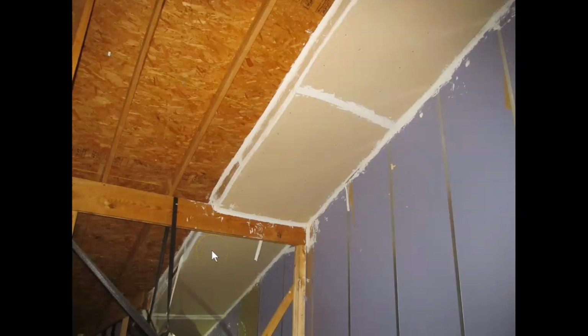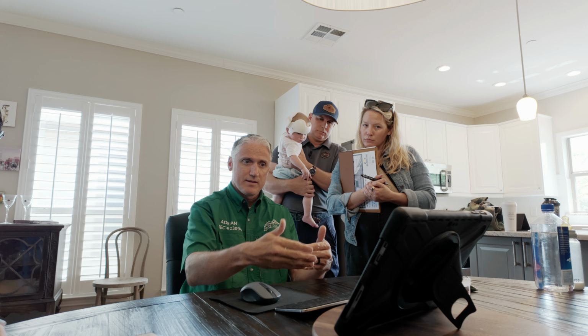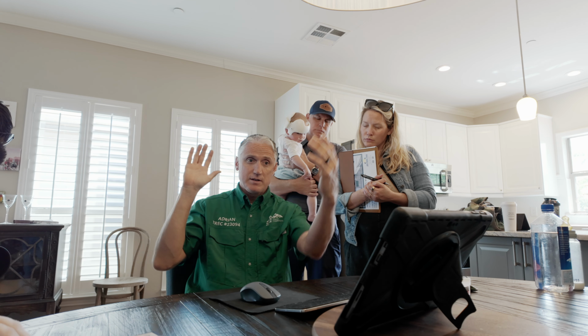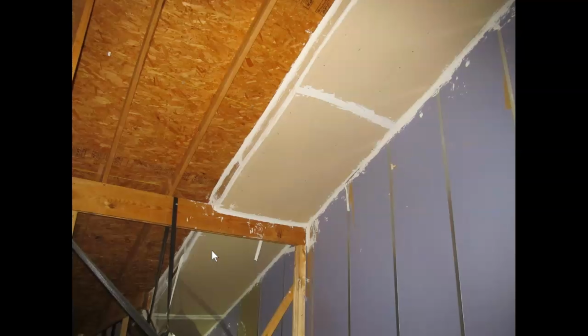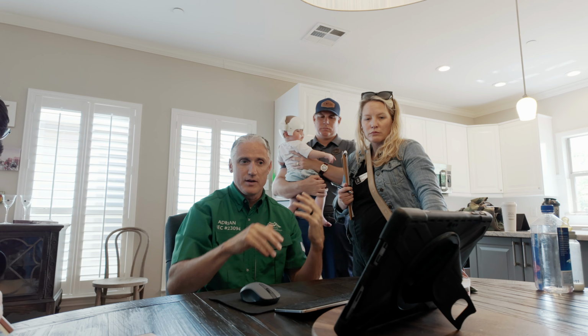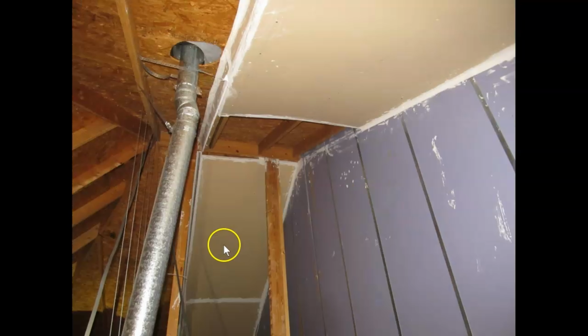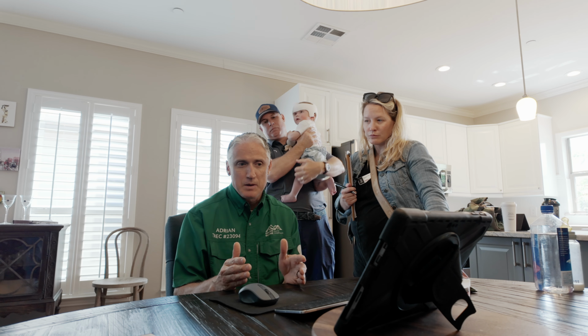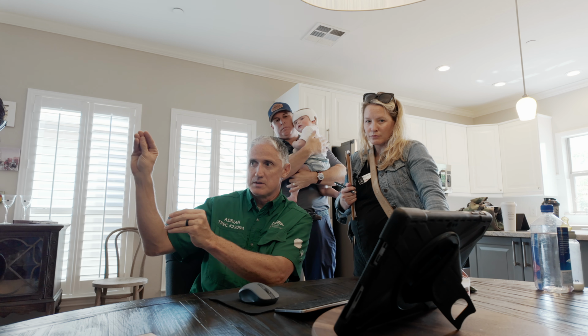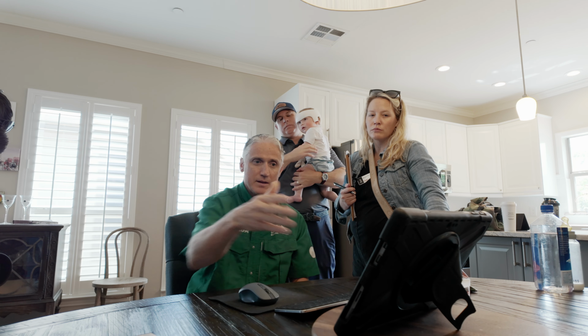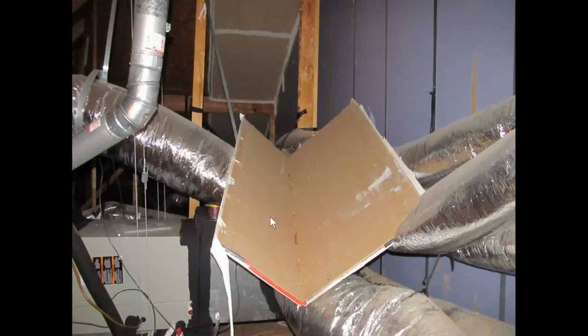I don't know if you recall, the last property had this fire separation from one unit to the next, and this one has the same thing, which is what I look for. This one also has it extending horizontally 4 feet, which usually doesn't happen. However, there's a spot that has fallen down, sitting right here. It took me until the end of the inspection to realize this is why the bedroom isn't cooling or heating properly, because it's compressing the ductwork and not allowing it to get the air it needs to properly blow.